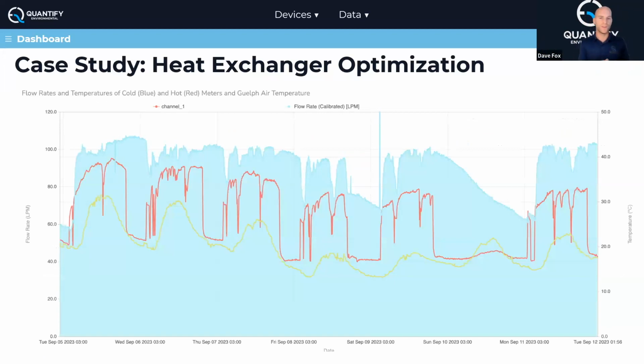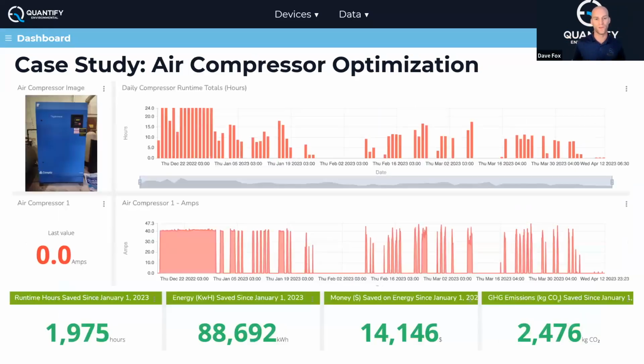On a very granular level, this is with a heat exchanger. If you have a heat exchanger that's not performing up to snuff, we put in multiple sensors - flow and temperature in and out, oil and water. This engineering team checks into a dynamic dashboard every day. This particular press heat exchanger had been a real issue, not providing the cooling it should for the last 3 months. What's actually happening inside that heat exchanger? Our data clearly showed them, and after about 3 weeks they took it out of commission, cleaned it, got it back up and running - flow increased, heating capacity and cooling increased. So it gives you very specific project data that you can use to optimize particular systems.